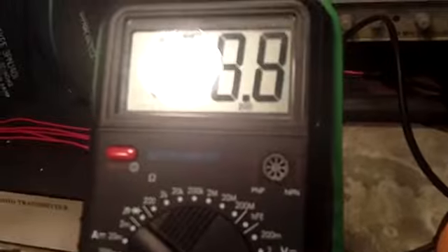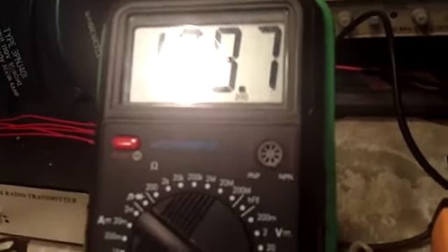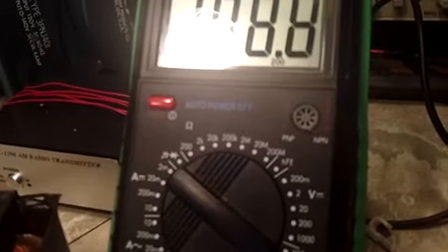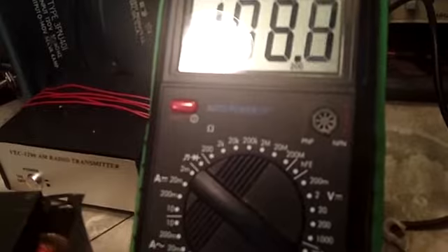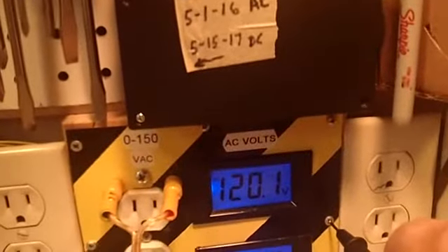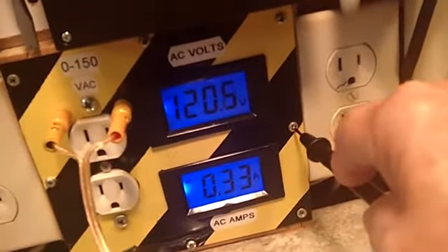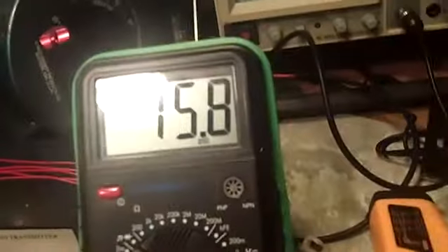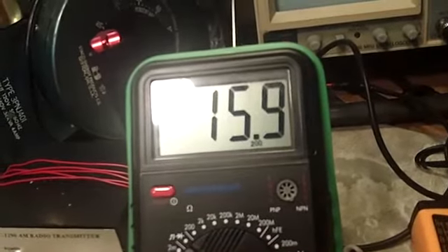But we do have a totally isolated output. There is no connection to the earth ground. I'm going to prove that by taking one of these leads loose and touching it to the earth ground, and we'll see what we got. Hang on. There you go. You see there's still 120.1. I am touching the earth ground, and if you look over here it says 16 volts.